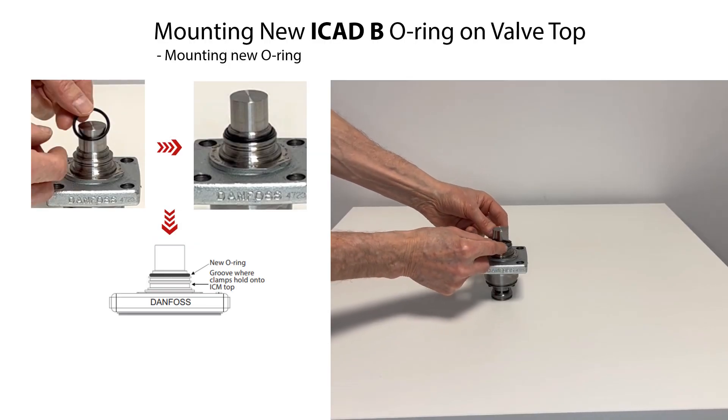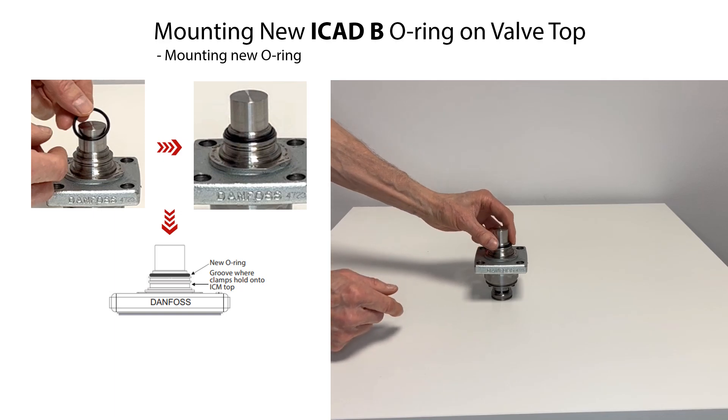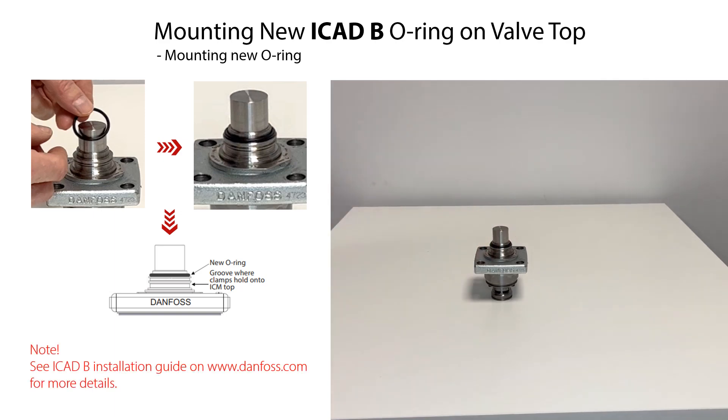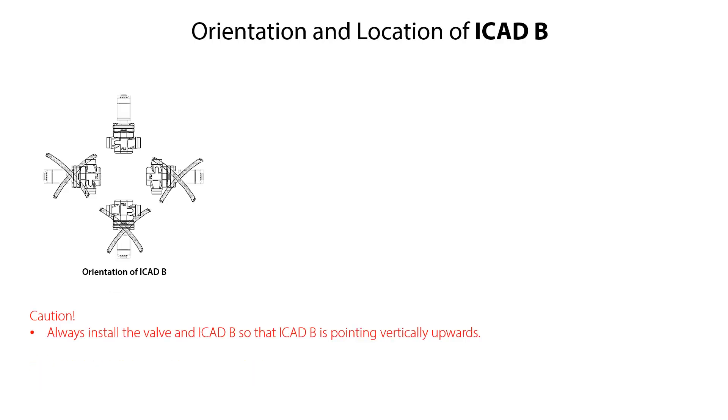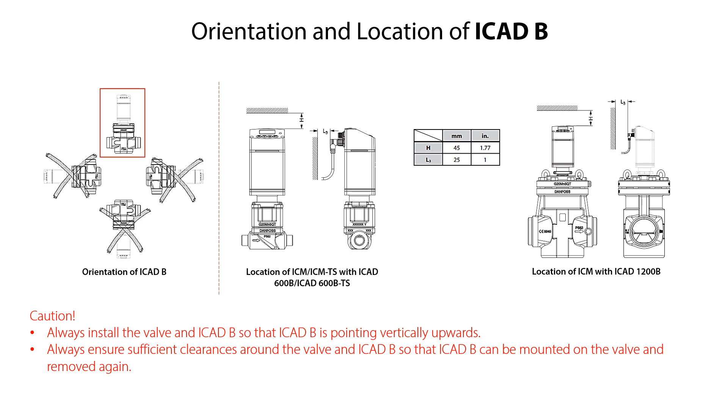Carefully mount the new ICAD B o-ring onto the valve top so that it is located in the first o-ring groove as specified. When mounting the ICAD B on the valve, always ensure that the valve is installed in the system so that the ICAD B is pointing vertically upwards once mounted, as illustrated. Also ensure sufficient clearances around the valve and ICAD B so that the ICAD B can be easily mounted and removed again if needed.